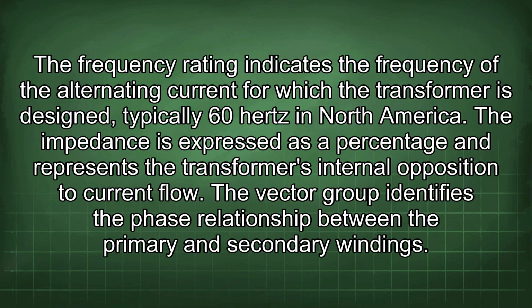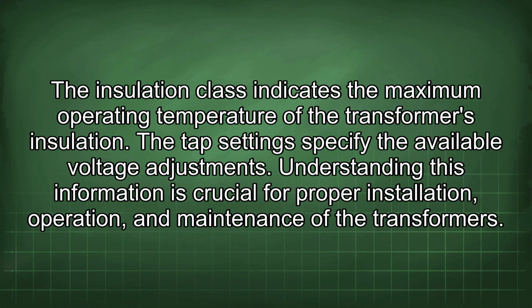The frequency rating indicates the frequency of the alternating current for which the transformer is designed, typically 60 Hz in North America. The impedance is expressed as a percentage and represents the transformer's internal opposition to current flow. The vector group identifies the phase relationship between the primary and secondary windings. The insulation class indicates the maximum operating temperature of the transformer's insulation. The tap settings specify the available voltage adjustments. Understanding this information is crucial for proper installation, operation, and maintenance of the transformers.